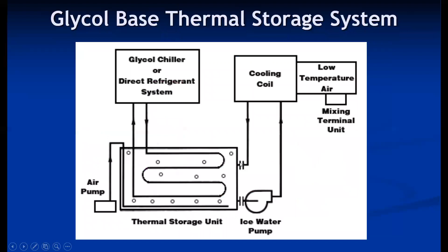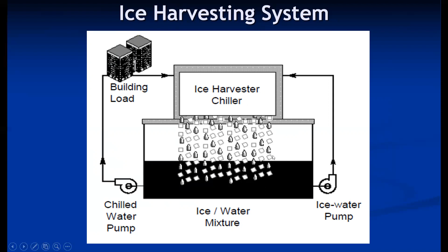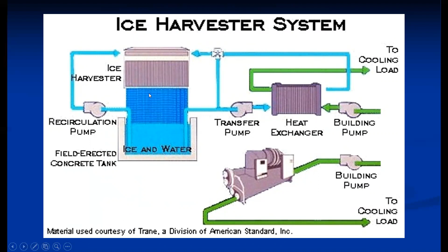Then the ice harvesting system. Ice harvesting chillers produce ice blocks. These ice blocks fall in the storage tank. So it is a mixture of ice and water, which is pumped to the building load. The return comes to the ice harvesting chiller. With the help of this warm water, the block releases and falls in the storage tank. In no load conditions, some energy is recirculated to the production of ice block. So ice water is recirculated for the production of ice block. So this is the ice harvesting system. A similar diagram, in colorful pictorial form. The working principle is the same as the previous slide.